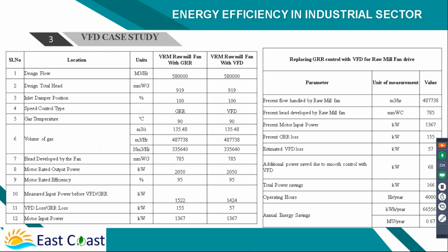So this is one case study of a cement plant, raw mill fan, where VFD application has taken place. They replaced the traditional GRR, grid resistance method, used for slip ring motors, which involves a resistance loss. Compared to that, the loss in VFD is much lower, so there is 166 kilowatt of savings. It's a big motor, so the savings are also more.